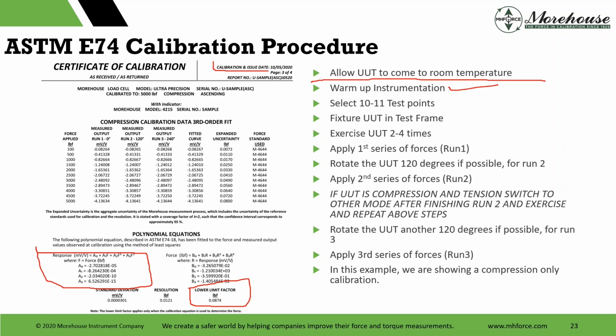Then, while we're warming it up, we're going to select our test points and start doing all of this other stuff, getting things ready. Select the test points, 10 to 11, recommend 11. We'll go over that. Then we're going to fixture the UUT in the test frame. And when I said 20 minutes, here's why 20 minutes. We really want 30, but by the time we start selecting test points and we fixture it in the frame and we exercise it 2 to 4 times, it's going to be at 30 minutes. So exercise the UUT 2 to 4 times, 2 is required.